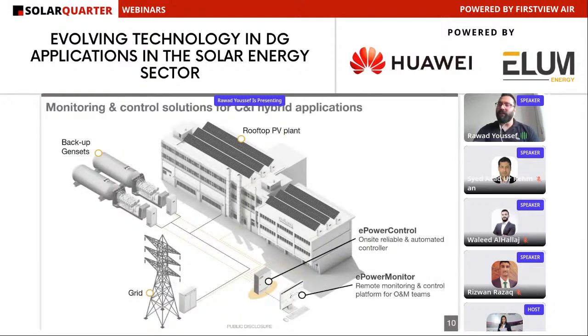As mentioned, regarding PV diesel hybridization, you need a controller to manage and provide certain features. The controller will be connected on the grid side to provide grid feed management - either zero export or net metering, depending on the country and project. Once there's a blackout and it switches to the backup genset, the controller will provide minimum genset loading, reducing fuel consumption and increasing PV penetration.